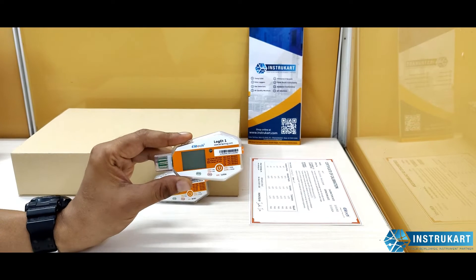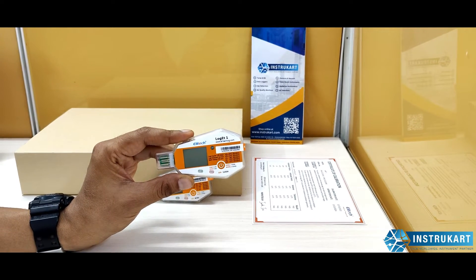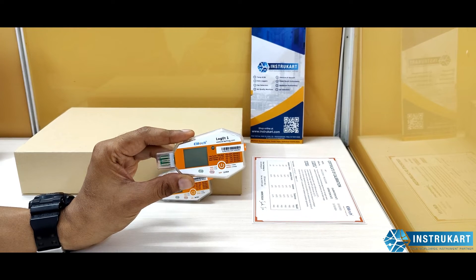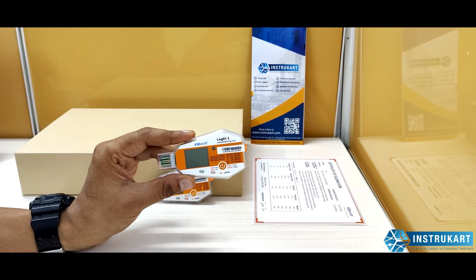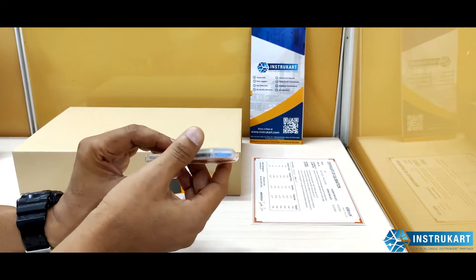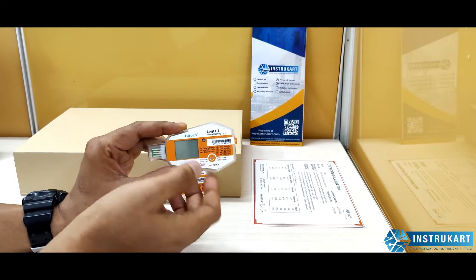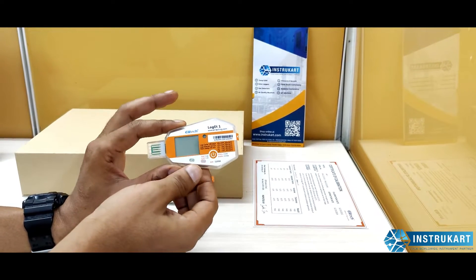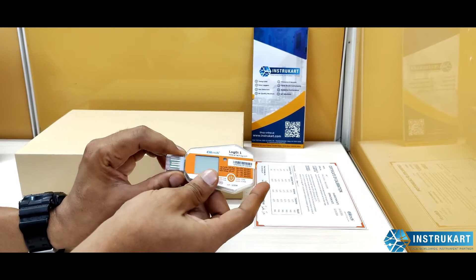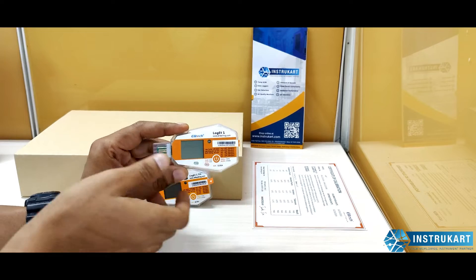This logger has an accuracy of plus or minus 0.5 degrees Celsius with a temperature range of minus 30 to plus 70 degrees Celsius. It can save up to 16,000 records at a time. When memory is full, you can plug it into a PC and generate a report in PDF format.